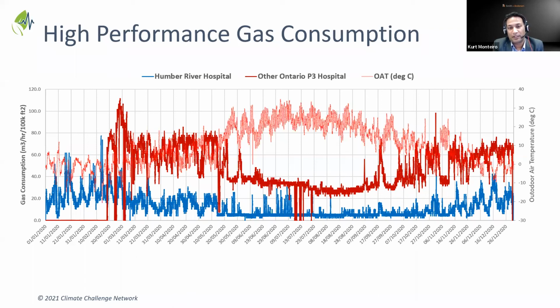The other thing is that in our effort to oversize the air handling units to reduce static pressure, we slowed down the velocity of the air running over the enthalpy recovery wheels. That increased the efficiency of those wheels far beyond traditional numbers, going from 77% up to north of 85 to 90%, effectively paying no energy penalty for having 100% outside air.